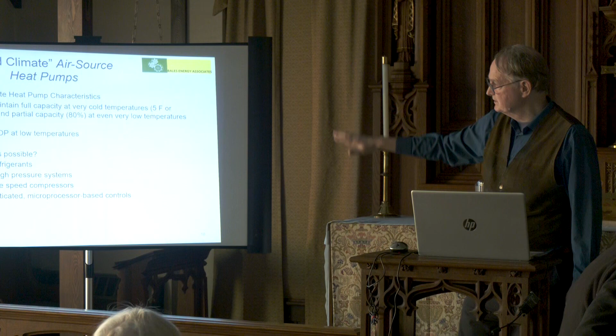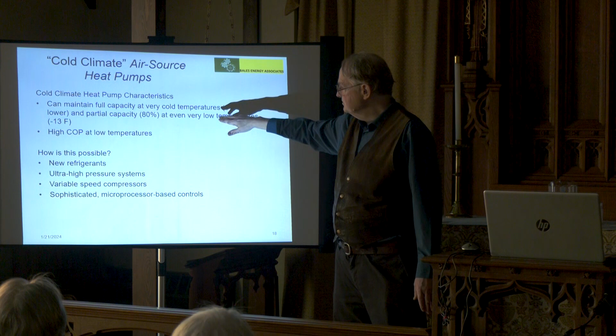There's a whole bunch of different brands that are good for this application. These units maintain their full capacity usually down to 5 degrees, and then they begin to tail off below 5 degrees. There are ways to deal with that: you can either oversize the unit so it'll still have enough output at low temperatures, or really it's just sizing for a lower temperature.